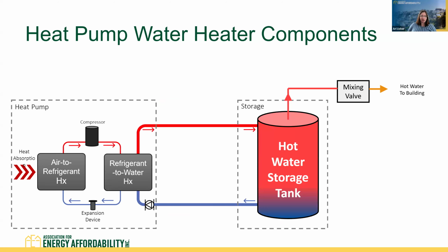Some of the components of a heat pump water heating system, whether this is unitary or central, we have the heat pump itself. So you can see there two heat exchangers, the air to refrigerant heat exchanger, and then the refrigerant to water heat exchanger. And in that side, cold makeup water comes into the heat exchanger, gets heated up, and is delivered to the hot water storage tank. So heat pumps are always paired with typically a large hot water storage tank.